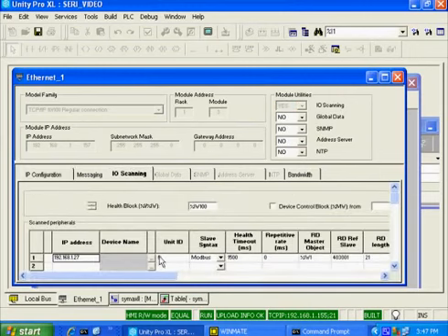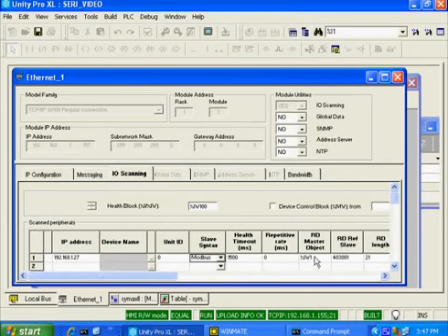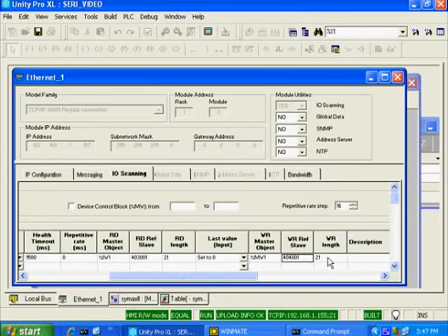The unit ID is 0, the syntax is set to Modbus, the health timeout is 1500, the rep rate is 0. The read master object is set to %IW1. The read slave is register 403001 with a count of 21. The write master object is %MW1. The write slave is 404001 with a count of 21.